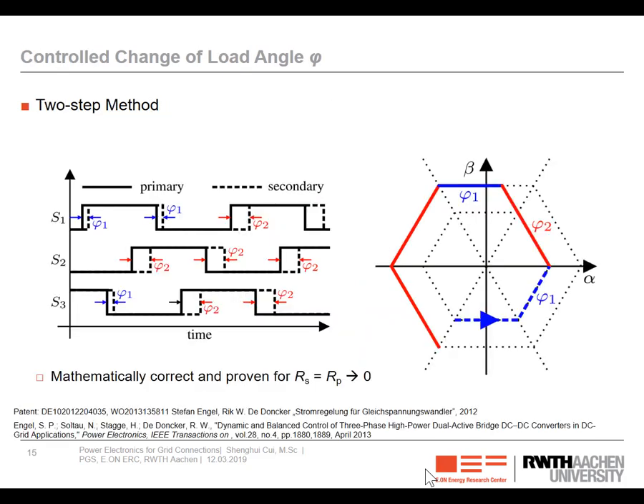Actually, the idea is quite simple. We just need to apply an intermediate phase shift during the process of the power change, so that originally it's working in this trajectory, and as long as the current trajectory reaches the target trajectory, then it is forced to go along the commanded trajectory. Then we can fully avoid overshooting of the transformer current and the DC current. So the principle is quite similar to space technology, where we are trying to change the orbit of artificial satellites from one altitude to another. At first it will accelerate, then it moves in another trajectory here, and as soon as it arrives at the target orbit, it will further accelerate and then stay in the target orbit.